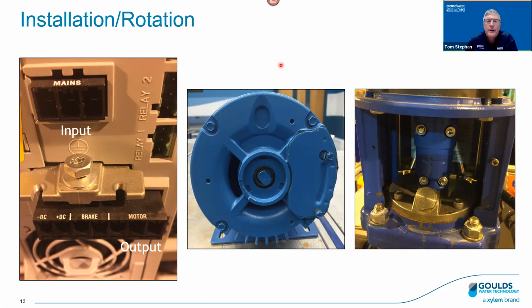And here we've got a couple examples of some surface mount. Surface mount's a little bit easier, right? Because we can actually see something turn. In this case, I'm looking at the back of a surface mount motor. I've taken off the dust cover and I can see the shaft rotation. So I could just bump it and visually see what direction that's going. Most motors will have an arrow to indicate rotation, and most of the time, always want to follow the arrow, but most of the time it's counterclockwise viewing from the motor end.